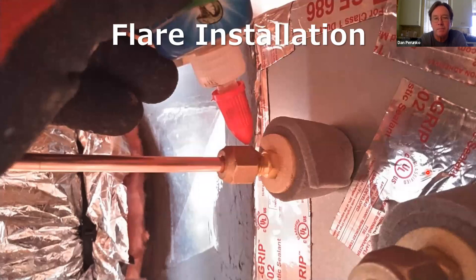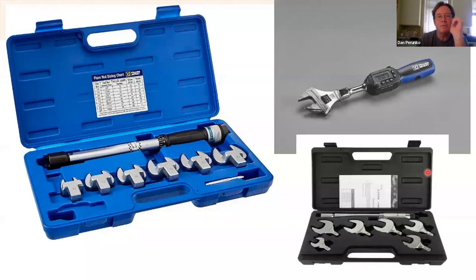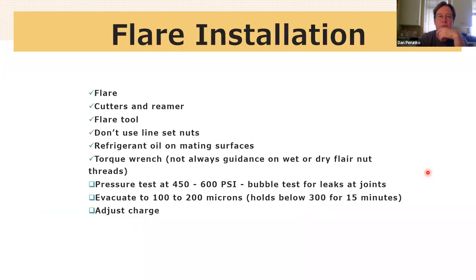There's a sealant you can put on the threads, although debate is out on whether or not this is necessary. It's important that we use a torque wrench so that we set the tension in the flare properly. And these are torque wrenches that are available.